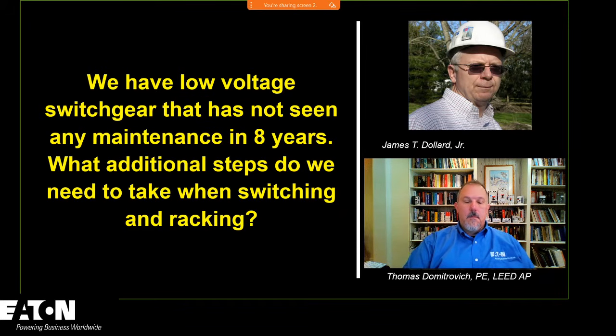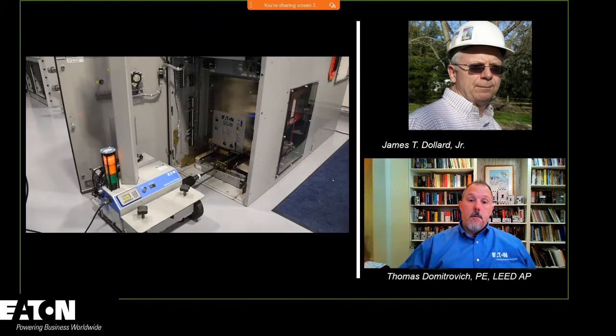So in a situation like this, I had a contractor come to me with a similar scenario. They were doing a switchboard replacement and had to open a 2,000 amp frame low voltage power circuit breaker that hadn't been maintained in years. I said, go to the owner and tell him to get that thing maintained. He called me back and said the owner's not interested in maintenance. So I told him to put in writing that just opening that device could cause the breaker to fail and he could lose all his equipment. In this case, that was a risk the owner was willing to take.